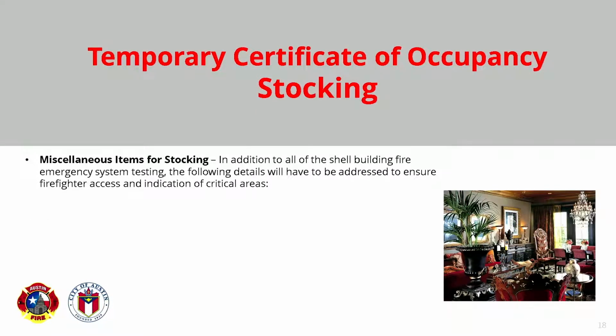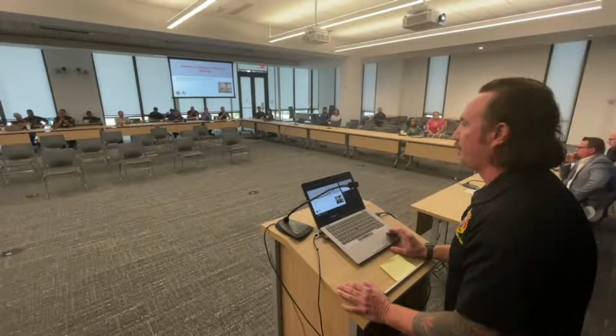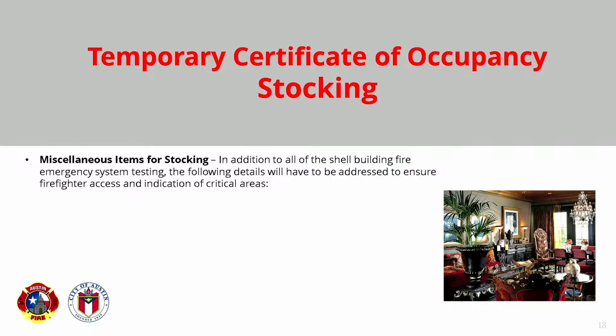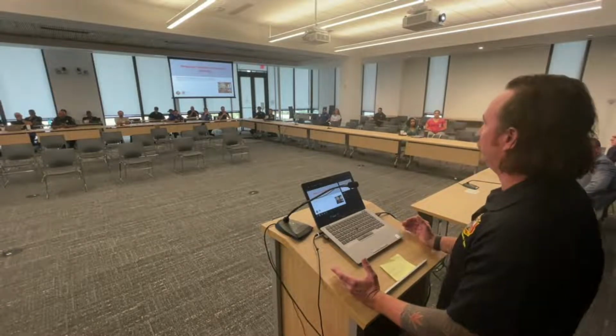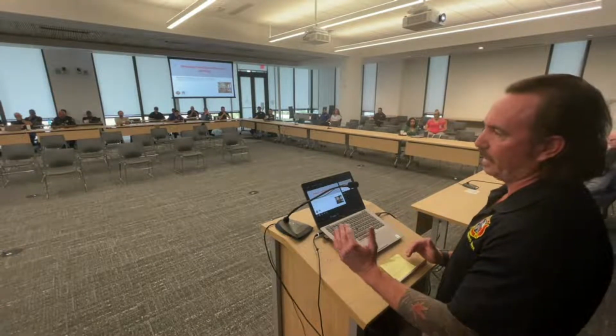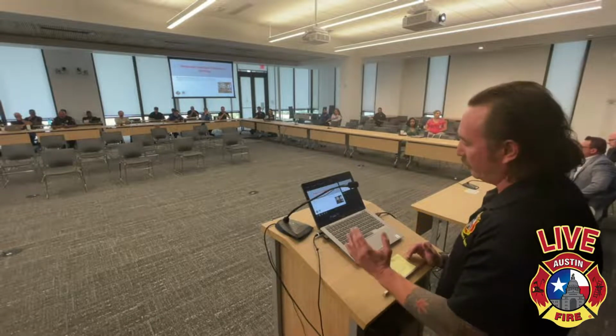So we've said TCO a ton of times. There's basically 3 different levels of fire final inspections. The inspection's the same, but at the end you can either fail, or there's the potential that if you paid for a TCO for stocking, that we can approve a TCO for stocking. If you paid for a TCO for occupancy, we can potentially approve a TCO for occupancy. Or if everything's good to go, then we can sign off on a fire final. Those are the levels that we're looking for. So that's kind of where your phasing comes in, to some degree.